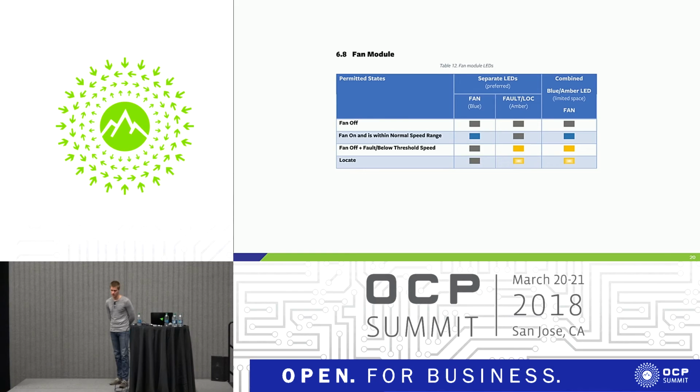So there's going to be situations where we have, let's say, a compute module, and let's say the NIC on that compute module has a green and amber LED on it, like you're saying. In that event, there's not a whole lot we can do if we're not the manufacturer of those modules. But we can ask for them to provide an additional, separate BOM for that. So in the case of the NIC 3.0, there's going to be multiple BOMs for whether it be green and amber or whether it be blue and amber like we want to do. So there's going to be some transition happening. Obviously, this has to only apply to future hardware. So this is a step in the right direction, I believe.